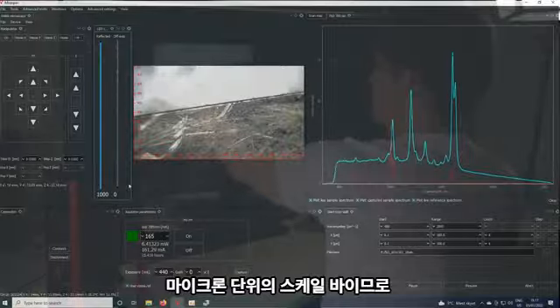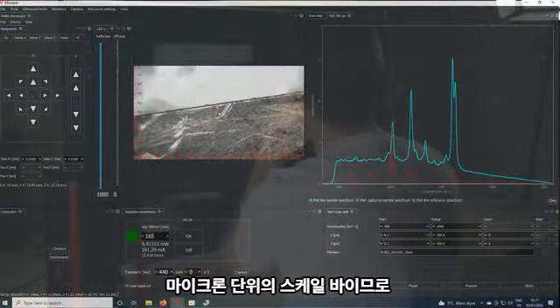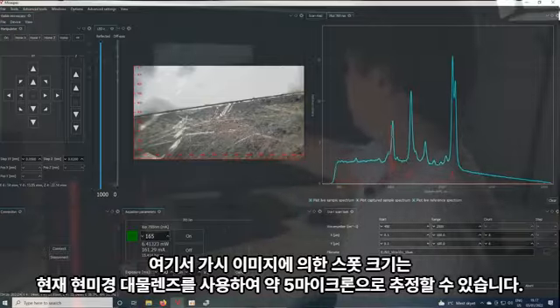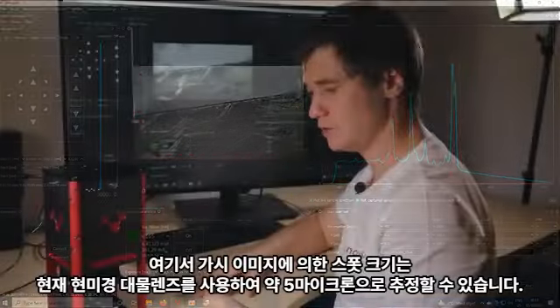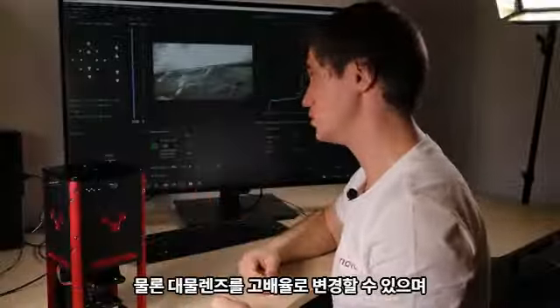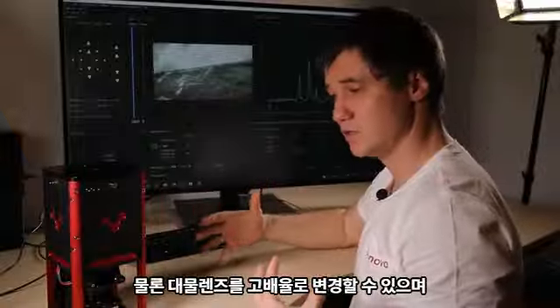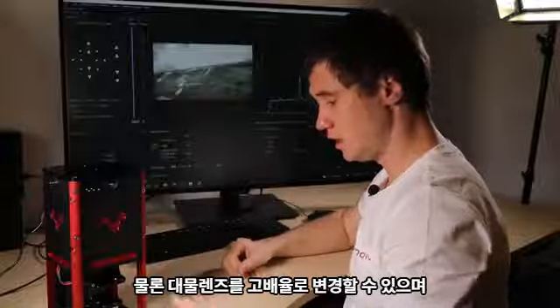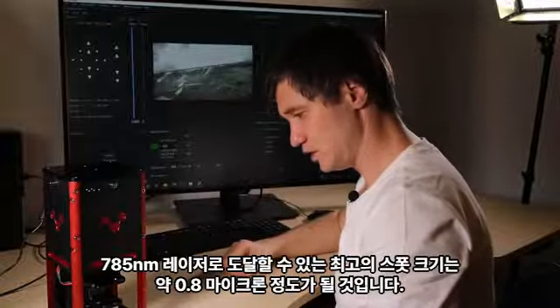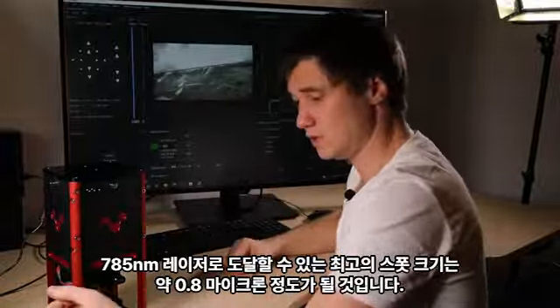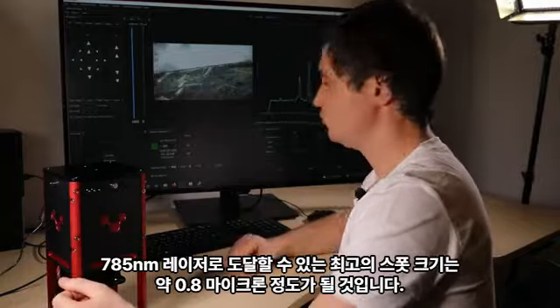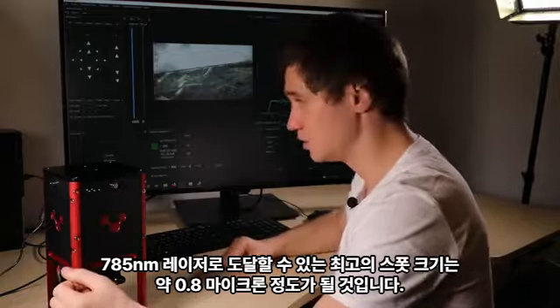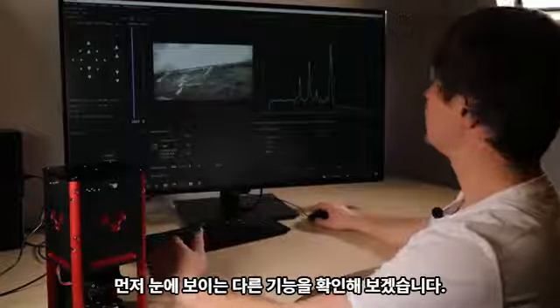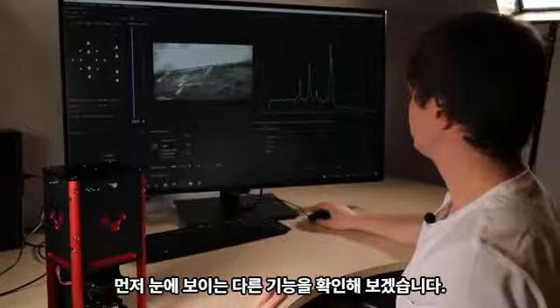This is the scale bar in microns. So the spot size here by the visible image could be estimated as around 5 microns with the current microscope objective. Of course, you can change the objective to a high magnification one, and the best spot size you could reach with the 785 nanometer excitation laser would be around 0.8 microns. Okay, let us check some other features.